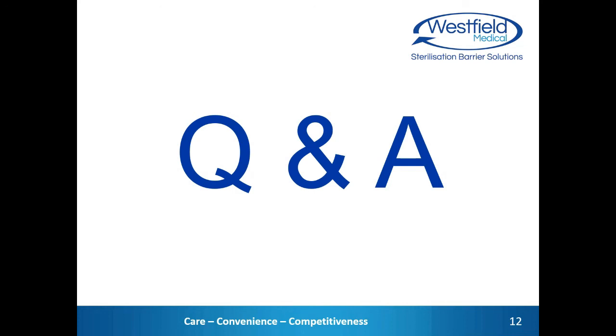What we really wanted to demonstrate with the study that we carried out and the results that were shown is that actually you need a very small amount of water to make HUMIPAK work. We used less than the recommended level just simply to demonstrate that, but the different sizes of HUMIPAK are designed for different sizes of tray. The assumption, I guess, is the larger trays have larger instruments, more instruments in them. The quantity being packed in the HUMIPAK is an unknown to us. Therefore, we had to look at recommending a level that gave us sufficient water to get the humidity buildup, but also a small amount of excess, so that if you've got high levels of residues on the instruments, some of which may already be starting to dry by the time it goes in there, you've got that little bit of extra water to make sure that the product performs as it should.